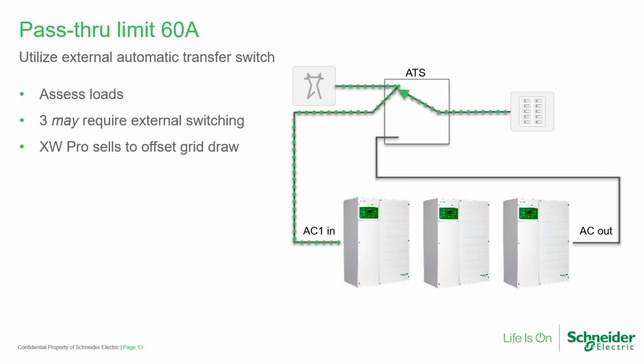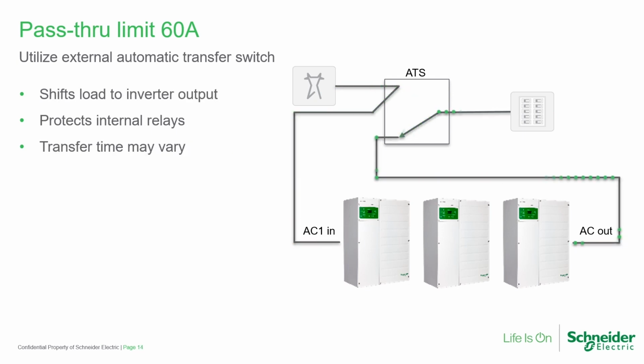Here is a system where you can see that the load is being supplied by the grid and it's also supplying the input side of the XW system. And here we see the loss of grid shifts all the load to the output side of the XW Pro system.